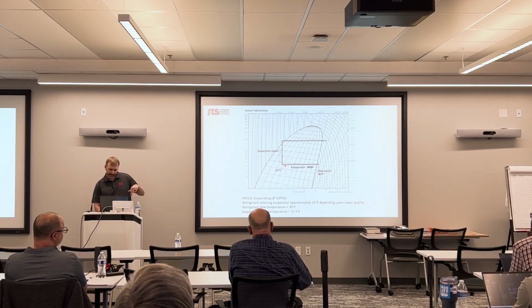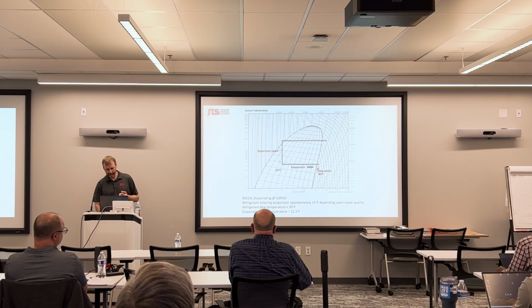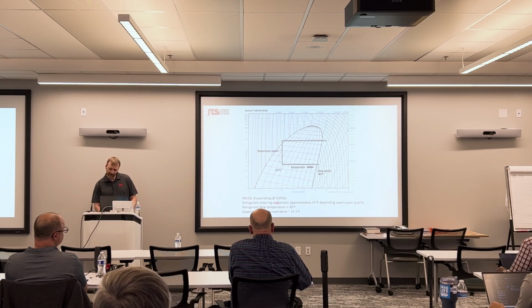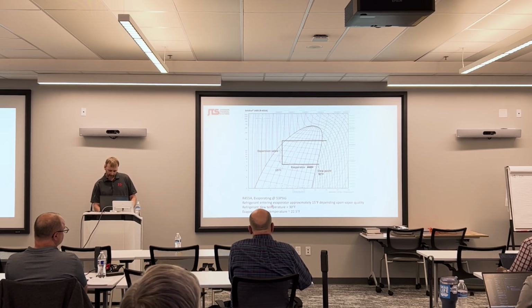Now, as that refrigerant passes through the evaporator coil, it's going to pick up heat, it's going to evaporate refrigerant, and as it does so, our vapor quality is going to increase until we get to the very edge of the saturation curve. At this point, we've got a 30-degree dew point. In the last pass or two of the evaporator, you're actually generating a little bit of superheat. So in this example, our R455A evaporating at 53 psi has approximately 15 degrees F entering the evaporator and approximately 30 degrees F dew point, and our evaporator mean temperature difference is kind of the middle point between this point and your dew point.